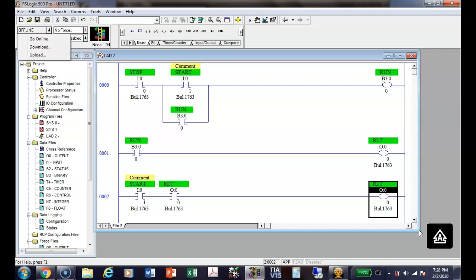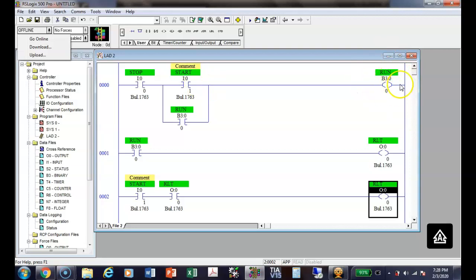Because now we can bring in a sensor as an input, and how many times can I use this contact right here? I can use it multiple times. So, it's really, really simplified things. But this is the big thing right here is getting rid of these control relays. So, when you get into a big relay, once you find out that 90% of the relays are in there are just for control. They're not in the power section. They're in the control section. And every one of those could be replaced by an internal coil.